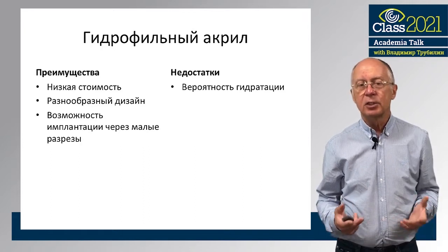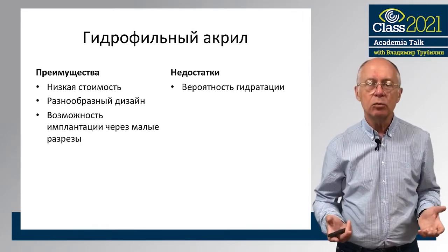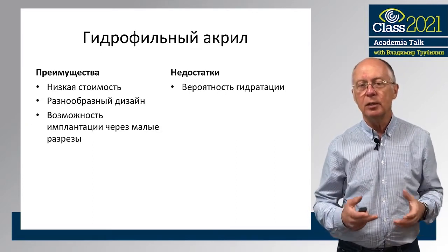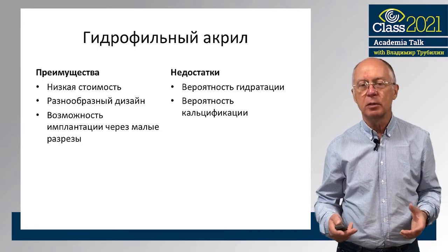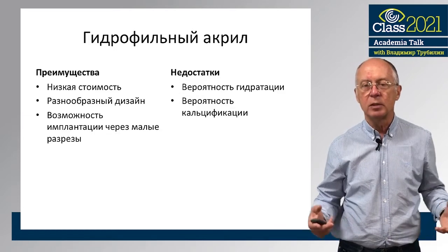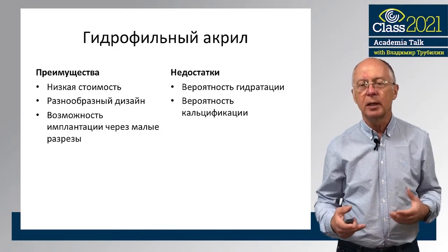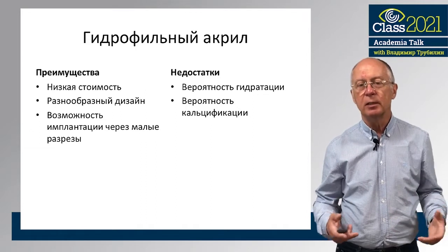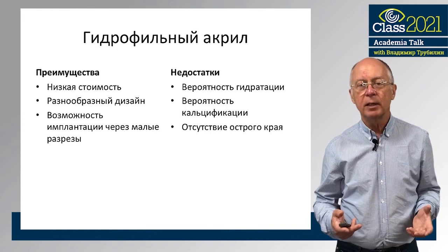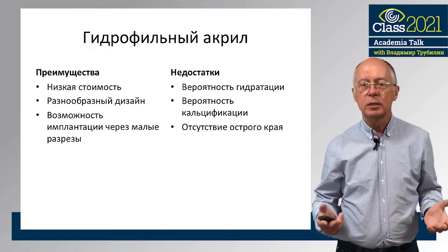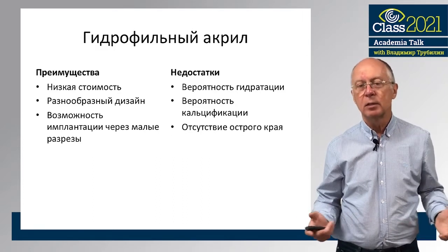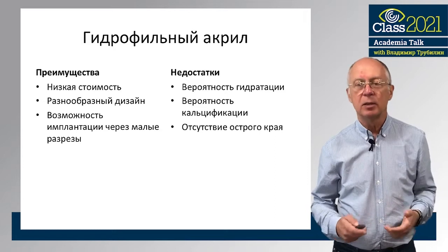Among the disadvantages is the possibility of hydration. Unfortunately, hydrophilic acrylic, once in the eye, can absorb water, which leads to a change in the optical properties of the lens. It is also a reason for calcification, which means that various salts can penetrate the body of the lens, and that can also cause clouding. Apart from that, it is difficult to make lenses from a hydrophilic acrylic with a sharp or straight edge, which prevents epithelial cell migration and the development of secondary cataract.